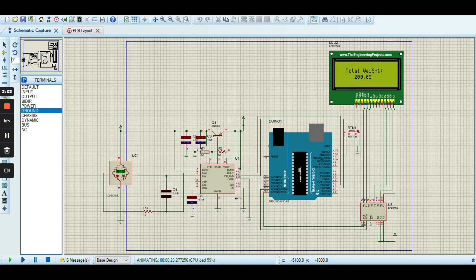Okay, next for the hardware part, the calibration tests have been carried out first. The calibration tests have been performed in 3 different types of tests: eccentricity test, repeatability test, and hysteresis test, using different types of load cell platform.